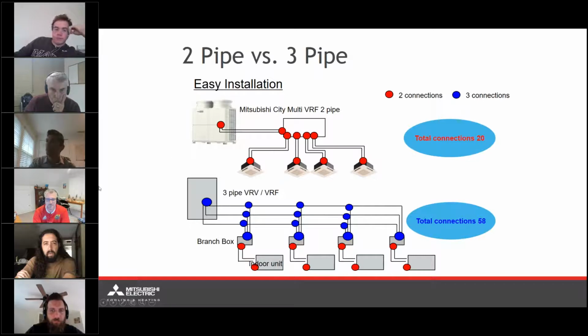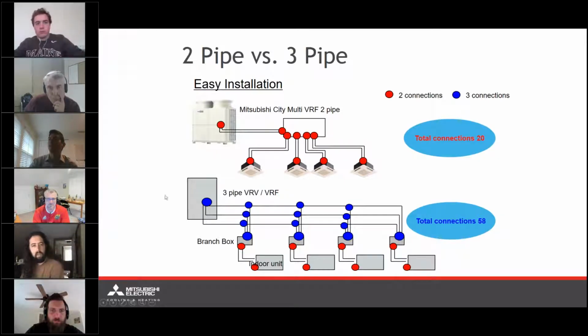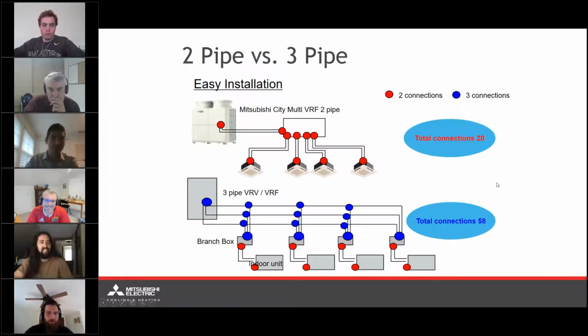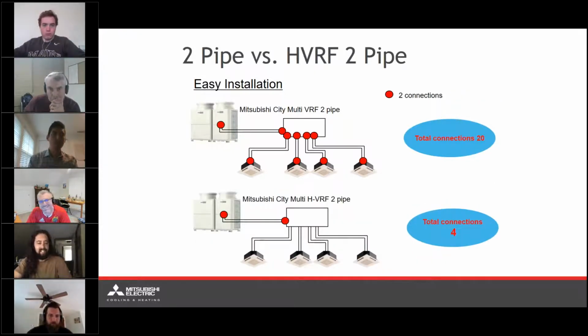Again, this is just for a traditional VRF system. For a 3-pipe system, again, everywhere you have a connection, you're going to have brazing. So ultimately, this is a demonstration for this particular layout. You're going to have substantially more connections, many more braze points. Now, I'm going to contrast that with a standard VRF and an HVRF system. So both of these Mitsubishi equipment.